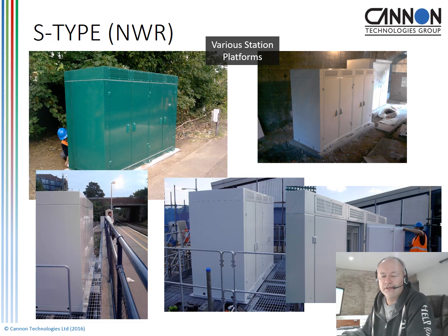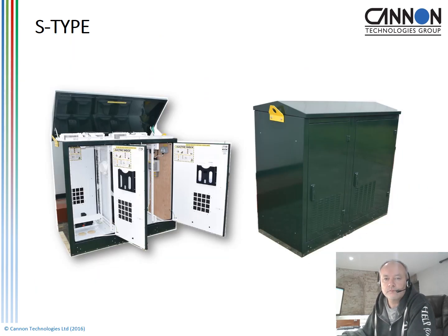This particular product was developed so it could actually be assembled on site as well, because in some of the locations they were unable to maneuver the product into site because they were in underground tunnels or areas where it was difficult to get access. So they had to be delivered in piece parts, and then our team of engineers assembled them on site. And this is a multi-bay broadband application, and actually shows an example where the roof is lifted so you can get access to the forced air cooling for maintenance and repair purposes, etc.